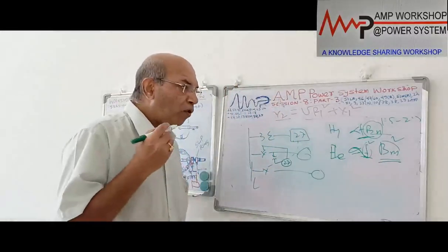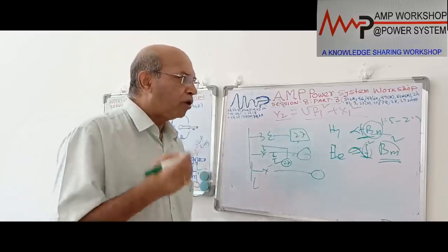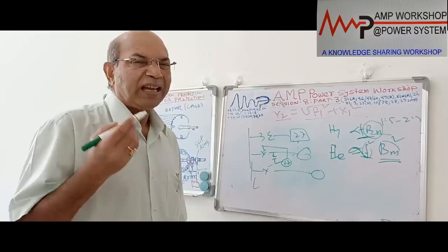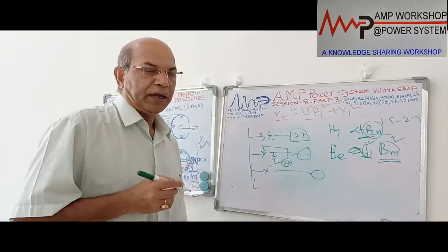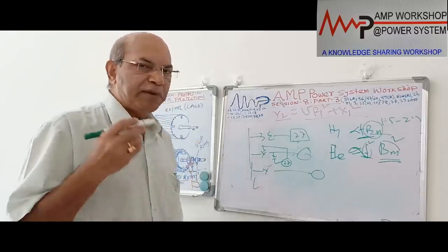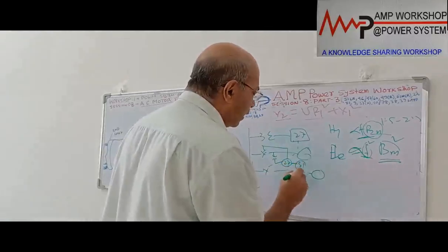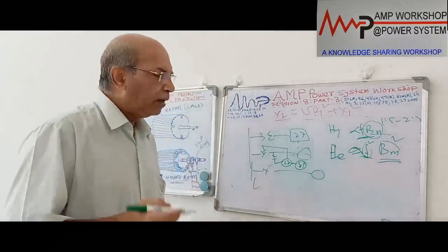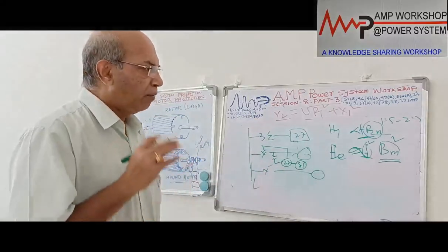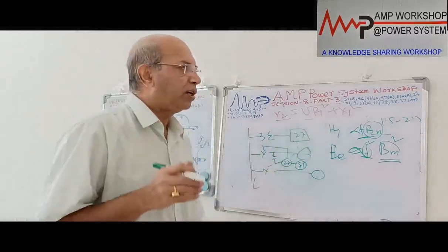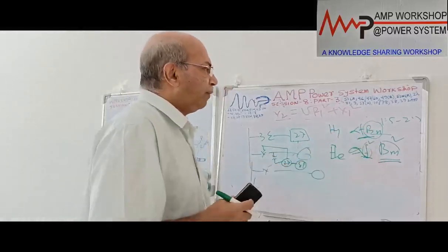So in case of low frequency, the motor efficiency will go down slightly, there will be more loss, and that loss will be converted to heat. That's why when there is under frequency there will be more heating effect. To avoid this, for big motors we provide under frequency protection. We connect an 81 relay, which monitors the frequency and gives the tripping command. But we apply it only for big size motors. For a small size motor, this loss is not very significant, because the losses compensate each other.